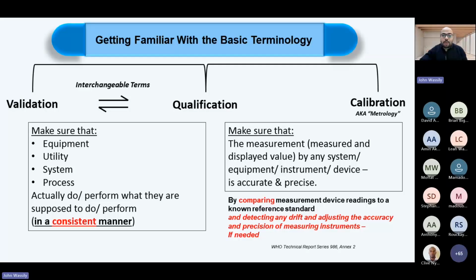Okay. Also, I want you to get familiar with the term of calibration, and you might encounter the term metrology. It's also known as metrology. This is to make sure that the measurement, either the measured and displayed values by any system, equipment, or instrument, is accurate and precise. So, for example, if we apply this on the scope of a sterilizing autoclave, calibrating its temperature sensors is to make sure that the temperature sensor is actually displaying and measuring accurate and precise measurements. This is done normally by comparing the measurement device readings to a known reference standard and detecting any drifts and adjusting the accuracy and precision of measuring instruments.